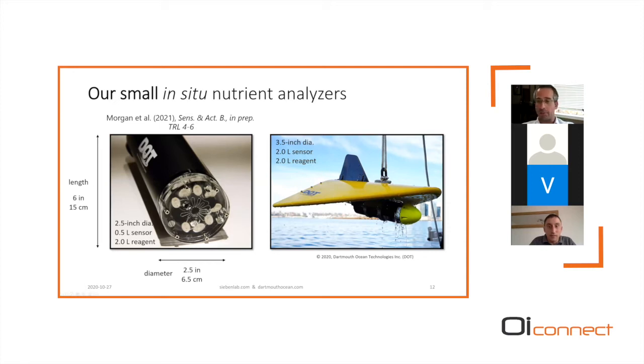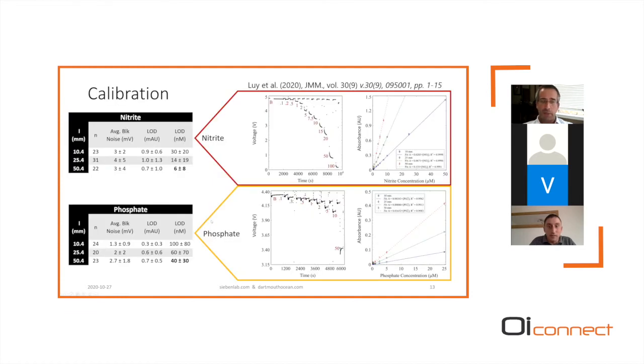And I encourage you to look up the publication that we're going to be submitting fairly soon. But the idea is we're really pushing down size. Our best sensor is 2.5 inches in diameter, quite small compared to existing systems, and our reagent and power consumption are dramatically lower. And the nice thing is we've done this without compromising performance. So our calibrations are as good, if not better, than most of the literature out there, because it's based on 100-year-old chemistry. So we're down at 10 to 50 nanomolar, depending on the chemistry we put through our channel and our absorbance cell.